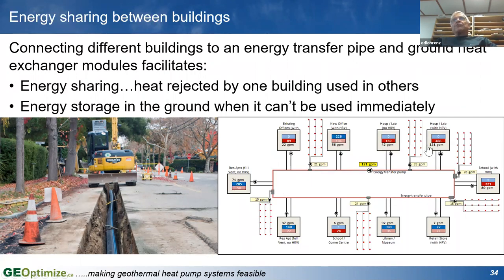Where we do need a ground loop is when most of the buildings are cooling or most of the buildings are heating. Energy that we dumped into the ground last summer, we can pull out this winter. And the ground becomes essentially an energy storage medium. And because we're sharing energy a lot, we can design a system that has less pipe in the ground. It's less expensive to build and works more efficiently. And simply laying a pipe in the street in front of the buildings can be done. That's being done.